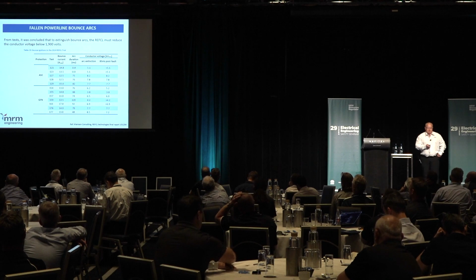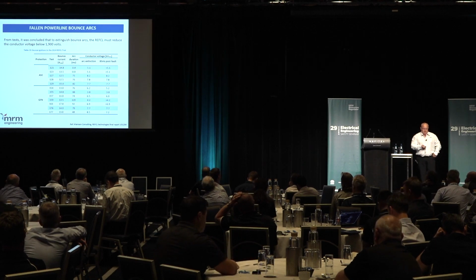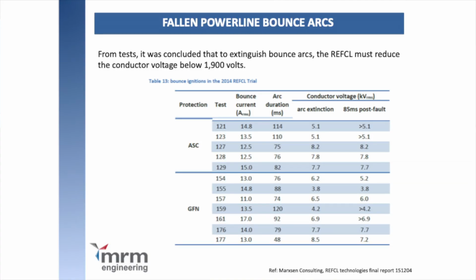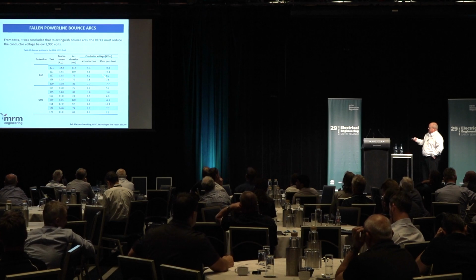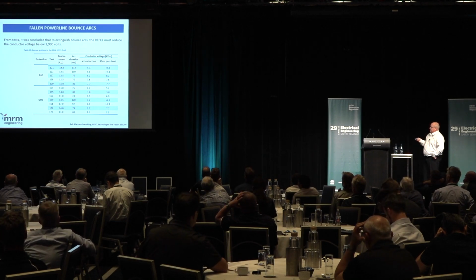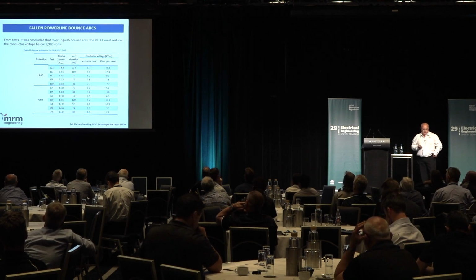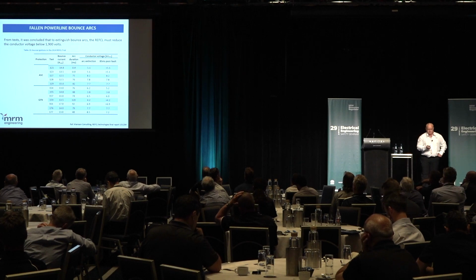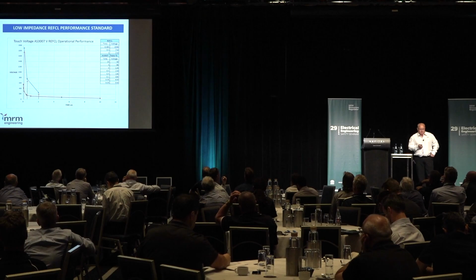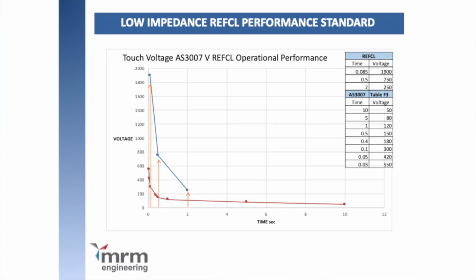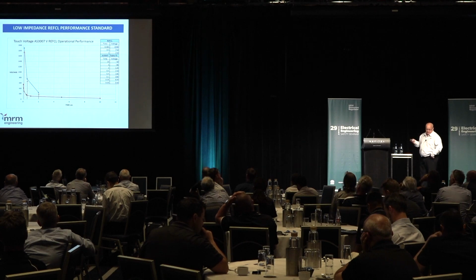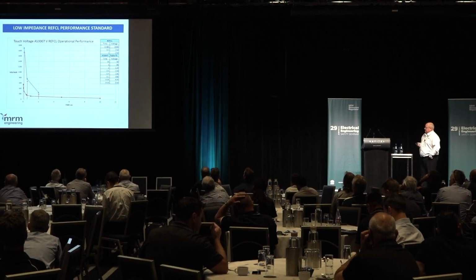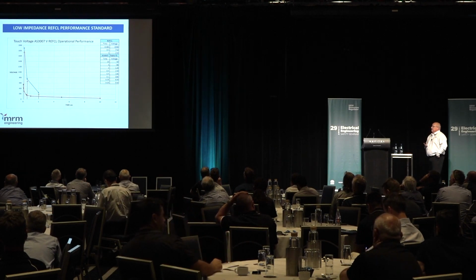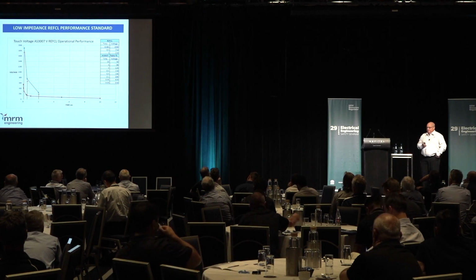So this is results of some of the tests they did. What they were trying to do there is verify that the times actually got down far enough and cleared the voltage. So you can see in the graph there's the voltage there. Even though that's what they measured at the fault, their timing is down below the 500 milliseconds for all those tests for the arc suppression coil and the ground fault neutraliser. So when we compare that to the touch voltages for AS3000, on the graph, the blue line is what the REFCL will clear to, and the red line is what AS3000 requires. So basically the REFCL won't give us any touch potential benefits, so our systems will still need to comply.